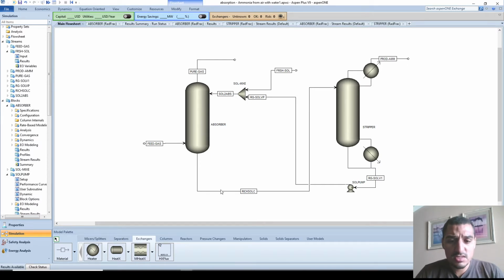So the heat exchanger here is going to exchange the heat of the cold stream with the heat of the hot stream. This hot stream is almost pure water, and this cold stream is water with ammonia. Regarding the routing of the streams in the heat exchanger, we mentioned before that the stream that is corrosive, higher in pressure, or more fouling should go to the tubes. And this stream is higher in pressure because it's coming at 6.5 atmospheres, and this contains ammonia, which might cause some corrosion, because ammonia with water might make some nitric acid or something like this.